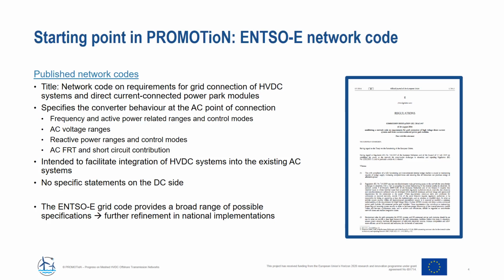It is intended to facilitate the integration of single HVDC systems into the existing AC systems. So the existing AC system is always the starting point, and the new HVDC systems should seamlessly integrate into the system. There are no specific statements on the DC side. Another thing is that the ENTSO-E grid code provides a broad range of possible specifications, and this is intended to provide the basis for further refinement in corresponding national implementations.